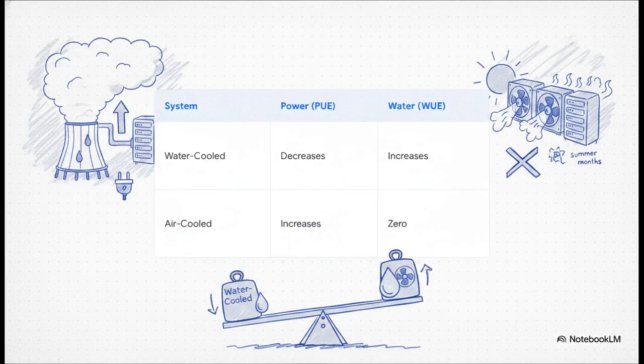Here's where it gets tricky, and this really hits the nail on the head of the whole engineering dilemma. To drop power usage, facilities often switch to water-cooled systems. But look at the trade-off: power goes down, but water usage, or WUE, spikes up—you end up evaporating millions of liters of local water. Or you go the other way, 100% air-cooled to save water, but then power usage goes through the roof during hot summer months. It's like this impossible teeter-totter. How do you balance it?